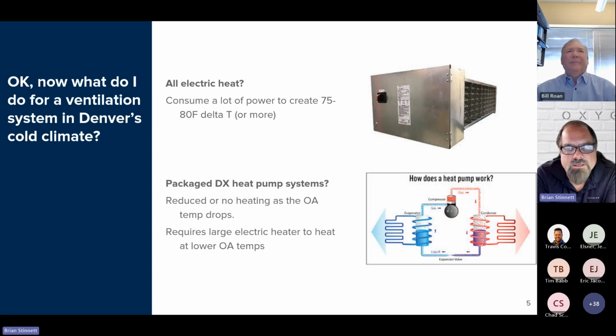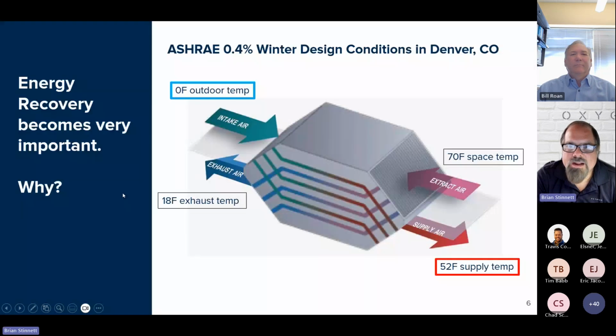So what other options? Well, we could look at a packaged DX heat pump system. It provides heating and cooling with the reversing valve in the refrigerant system. The issue with those systems is once you start getting into the 30 degree or maybe even 40 degree Fahrenheit outside air temperature, you have reduced or possibly no heating available. So they're not very good in cold climates because of the lack of heat when the outside air temps start dropping. So what else? Well, that's when we start looking at energy recovery. Energy recovery becomes very important when you're trying to do ventilation in a cold climate and stick with electrification principles.